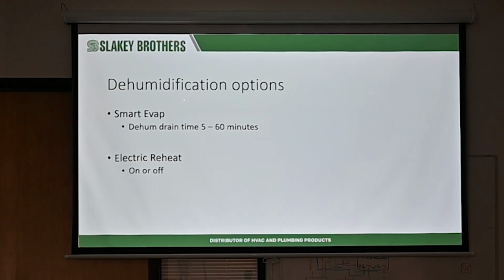If you are doing dehumidification, you've got to give that unit time to drain the water. What this little smart evap does is force the unit to turn off. No airflow, no heat, no cool, nothing for 5 to 60 minutes. That gives that water time to come down off of that coil to drain out. Because if you turn on even the airflow, just fan only, as soon as you stop dehumidifying, all that air goes through that moisture and right back in the house. That air will pick up that moisture again that's on that coil and throw the humidity right back into the home. So that's what this feature is for: it gives it time to get that coil dried out as much as possible, let that water drain out. And you're going to see this option both in furnace and in a fan coil.